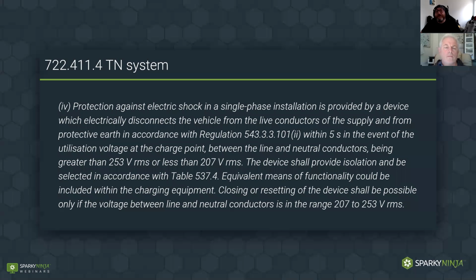If the utilization voltage at the charge point between the line and neutral is greater than 253 or less than 207. So we're starting to use voltage monitoring. So voltage monitoring is the way to protect with this method. The device will provide isolation and be selected in accordance with table 537.4. That's the table back in chapter 53 that tells you about devices that are suitable for isolation, functional switching. Yeah, it just means it should be recognized as a device for isolation.